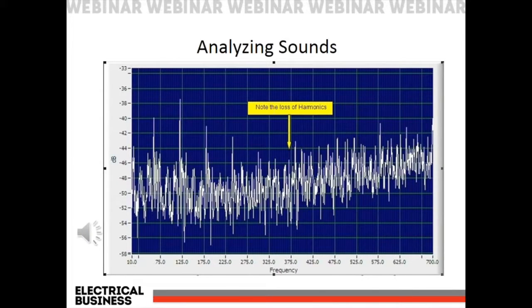Going into our next one, we have tracking, and obviously tracking has now progressed further. Tracking has found a low current pathway, and that pathway is going to give us a different sound, because it has now developed into some flashover. And when we say flashover, we're obviously referring to arcing. In this case, we would sometimes call it baby arcing when it comes to tracking, and it can sound a lot like this.